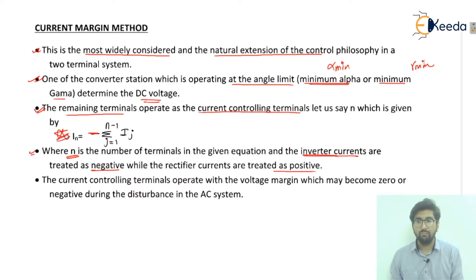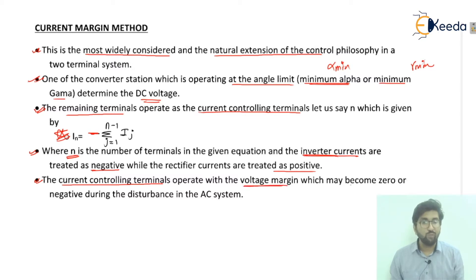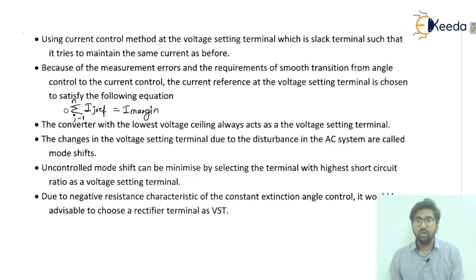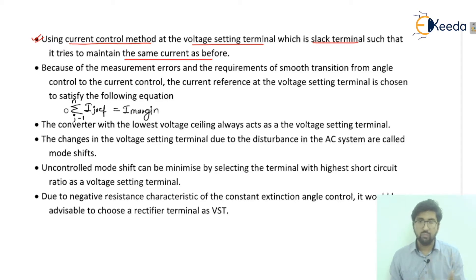The current-controlling terminals operate with a voltage margin, which may become zero or negative during disturbances in the AC system. Using the current control method, the voltage-setting terminal acts as a slack terminal, trying to maintain the same current as before — whatever the current was in normal conditions remains the same after a disturbance.